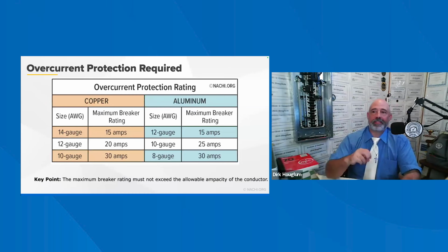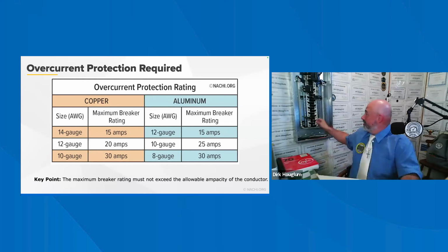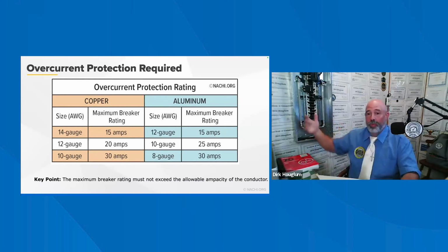The overcurrent devices consist of circuit breakers or fuses. They are installed at the beginning point of the circuit where the conductors receive the electrical supply. The breaker prevents conductors from carrying too much current, or above that determined allowable ampacity. The breaker will automatically open up the circuit and protect the conductors if the current is too high and may create a very high temperature hazard. So we don't want that to happen. That's why these circuit breakers will turn off when they have that.